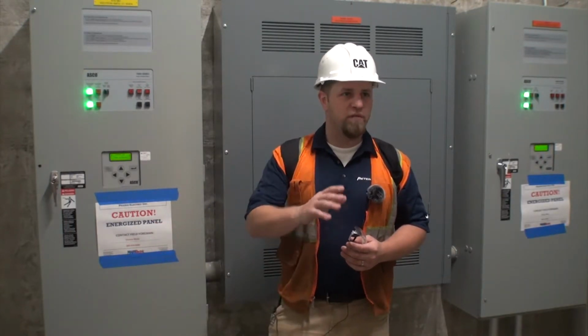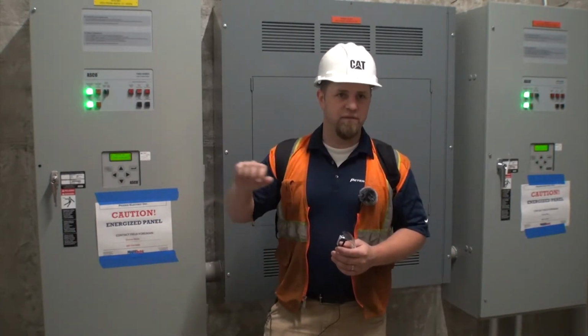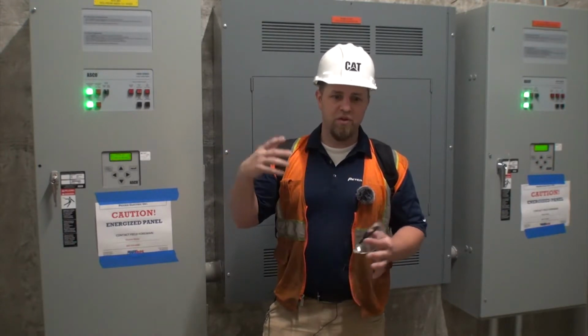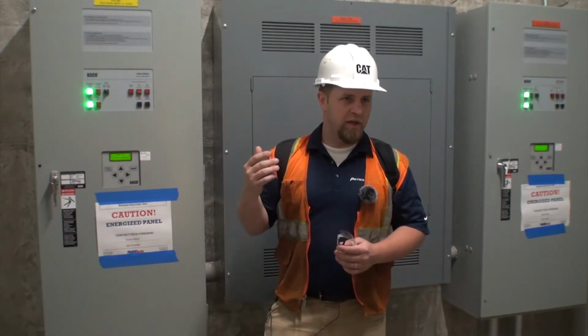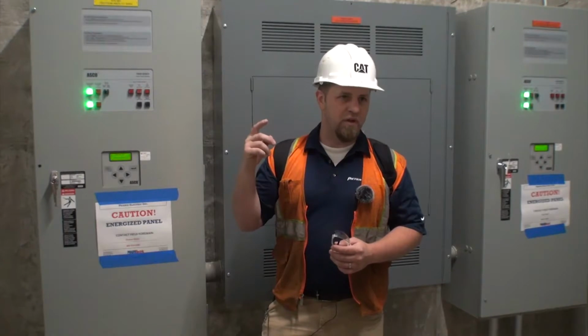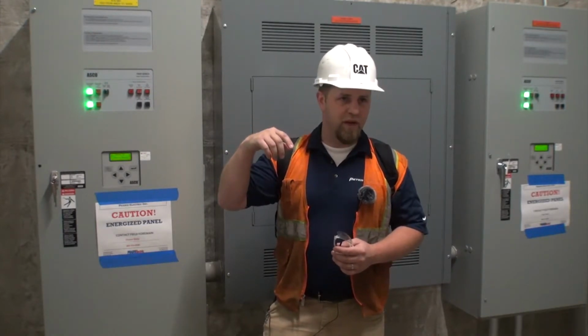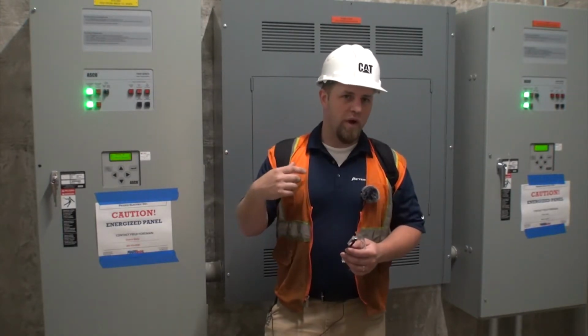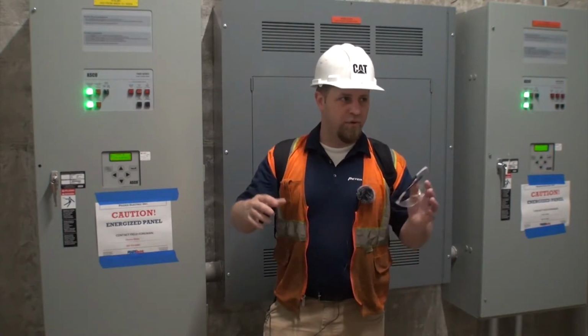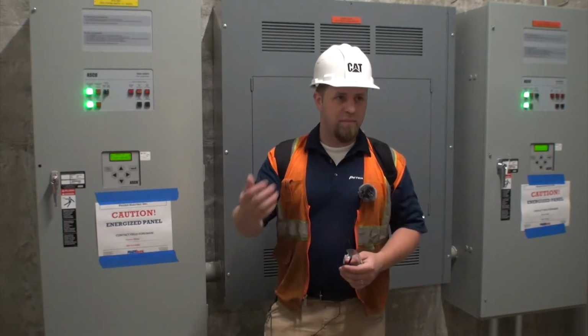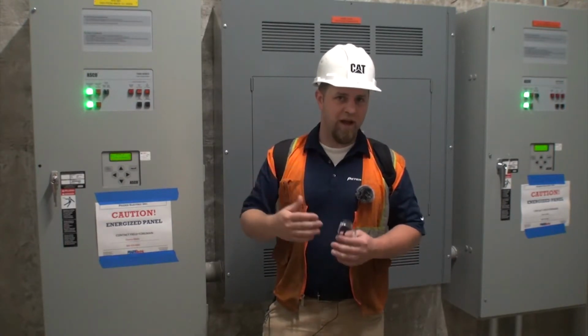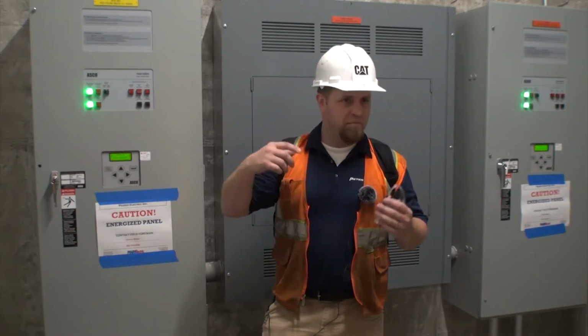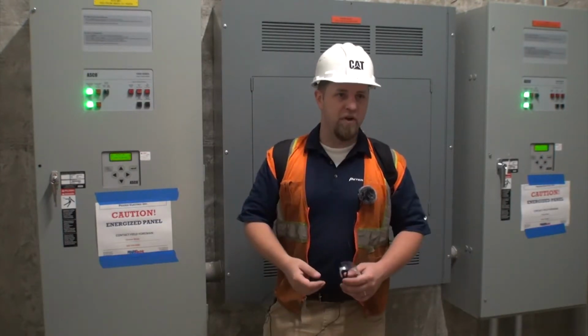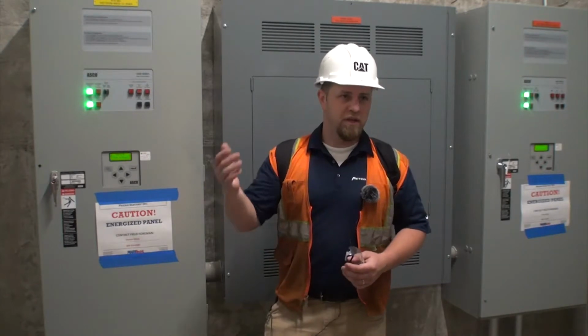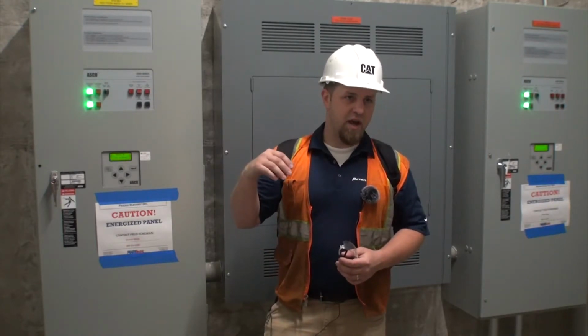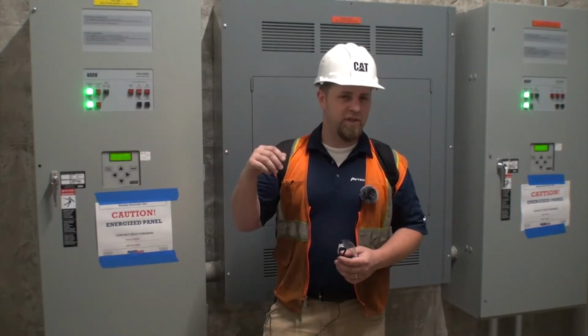I would recommend not doing the monthly transfer automatically. I would make sure one of you guys is here to actually flip them. So my usual routine on a weekly is to go up there right before it's going to run, check my fluids, everything else, close the doors, walk away. You're going to hear it start, go fool around, do whatever you're going to do. Right before it's about to shut down, go back out there, open up the doors, make sure there's no coolant all over the ground, oil all over the ground. Take your readings, it'll shut down, make sure it's ABCs.